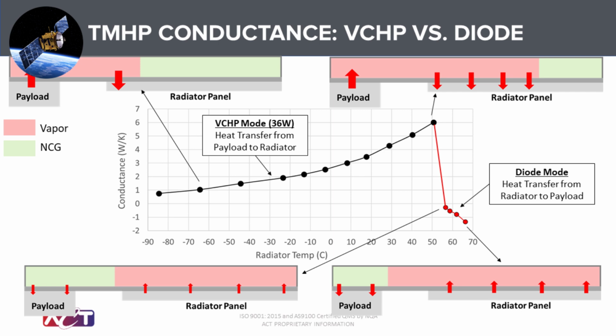So the payload increases in temperature slightly and compresses the non-condensable gas towards the end of the condenser. Or the other way, the sink temperature increases and generates this pressure increase, but because the vapor pressure increases faster than the non-condensable gas, according to the ideal gas law, the front goes more to the right and opens more of the condenser. So then payload temperature fluctuation is less than the sink temperature.